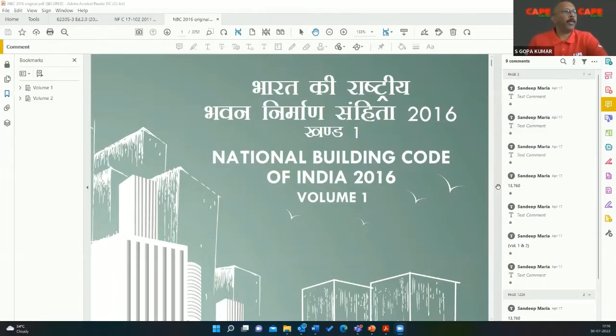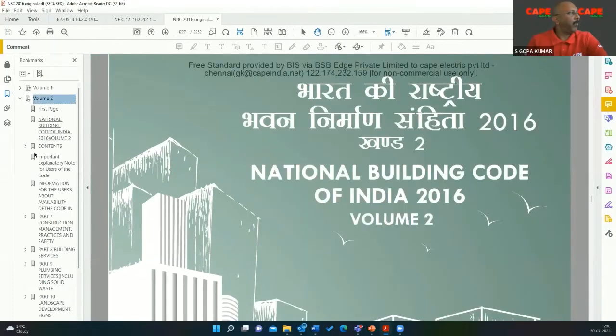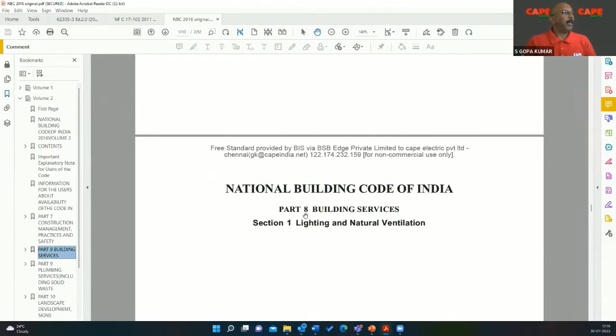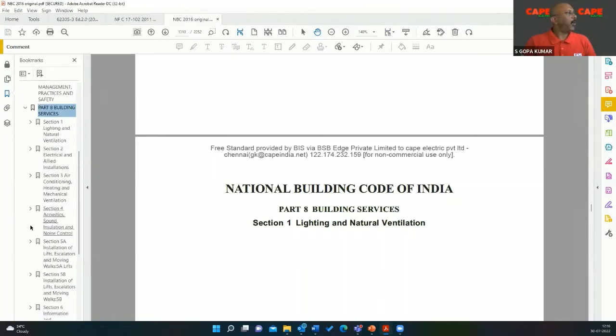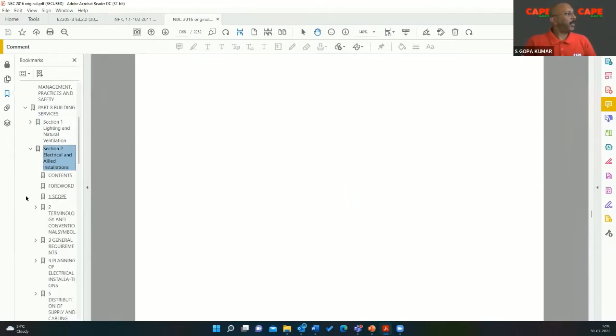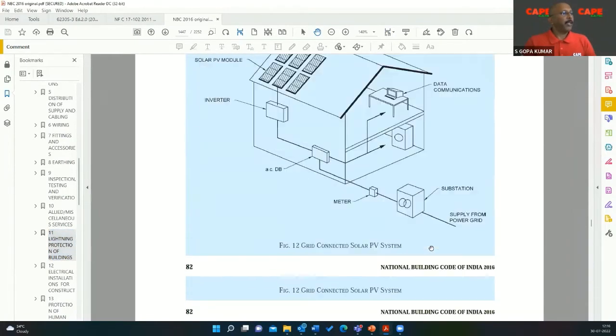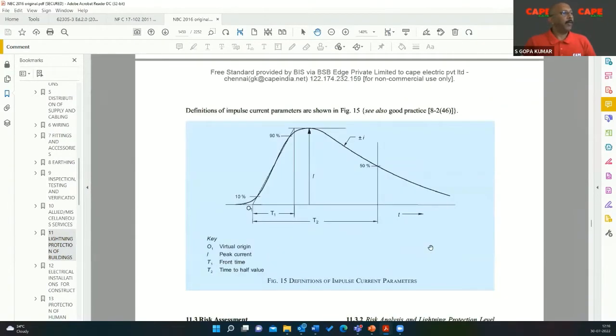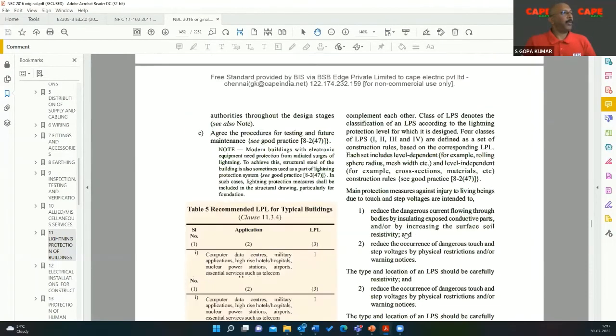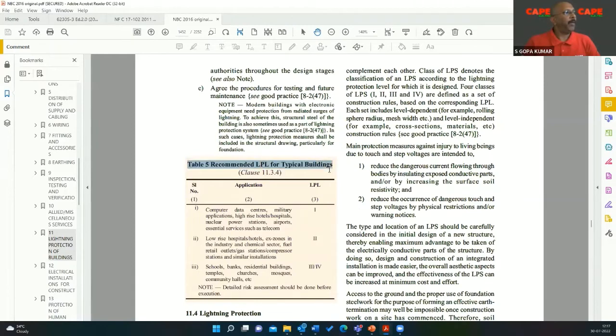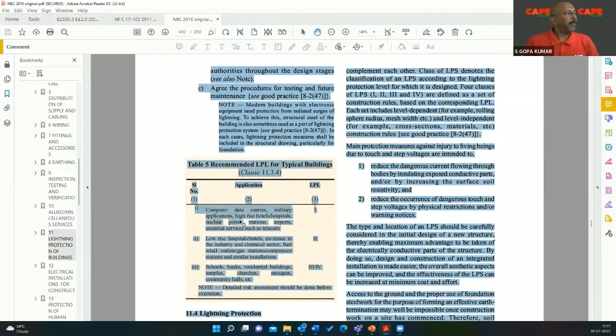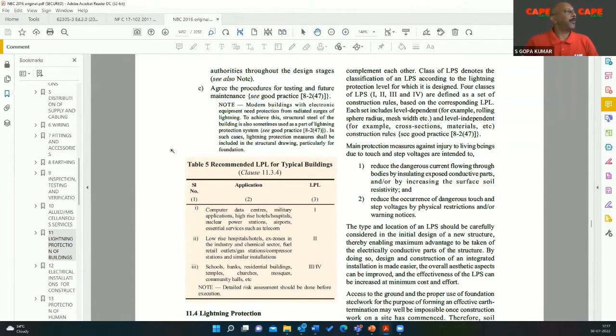I am going to share the National Building Code of India. Here is the National Building Code of India 2016. Go to Volume 2, then Part 8, which talks about building services. Building services consists of several sections. Section 1 is about lighting; Section 2 is about electrical and allied services. Go to Section 2, then Clause 11, which talks about lightning protection of buildings. Scrolling down, you will see Table 5: Recommended LPL for a typical building — computer data centers, military applications, and so on.